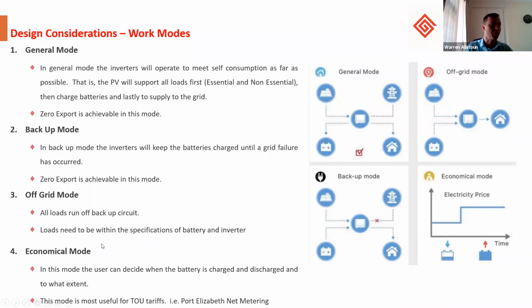And then the fourth mode is the economical mode. In this mode, the user can decide when the battery is charged and discharged and to what extent. This mode is most useful for time of use tariffs. For example, in Port Elizabeth, their net metering works on time of use. So this economical mode can be used to maximize the return on such projects.